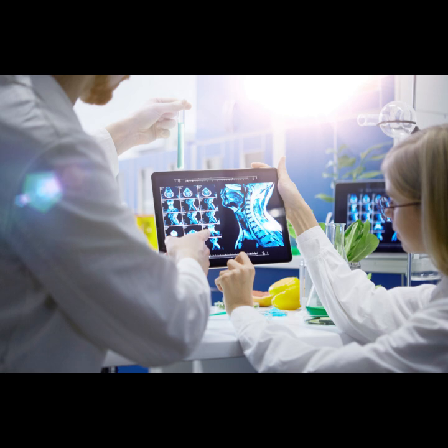EPI is the workhorse for fMRI, diffusion tensor imaging, DTI, cardiac imaging sometimes, anything where the anatomy or physiology is changing rapidly. But there must be a downside to going that incredibly fast, right? Pushing the gradients that hard. Absolutely. That breakneck speed and rapid gradient switching make EPI highly sensitive to any imperfections. It's very susceptible to T2* decay effects, magnetic field inhomogeneities, and chemical shift artifacts. Leading to image problems. Yes.